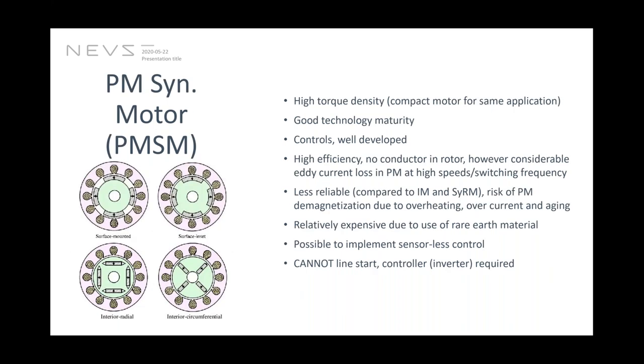Now, the second type of motor is the permanent magnet synchronous motor. It has quite high torque density and is very much liked and used in the automotive sector. It has good technical maturity, the controls are well developed, and it is very efficient because there are no conductors in the rotor. However, for VFD application, there might be quite high eddy current losses in the permanent magnets, which might be problematic in itself.